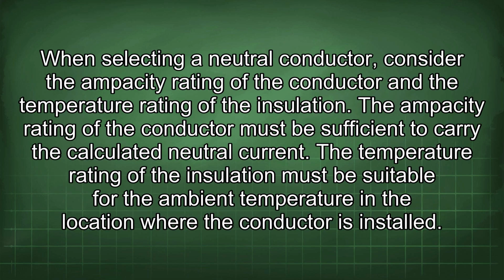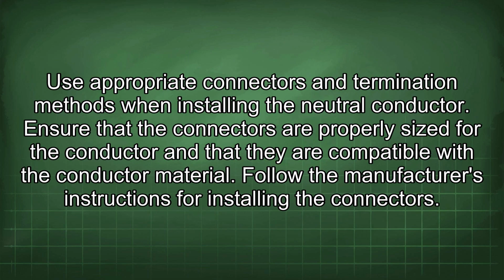When selecting a neutral conductor, consider the ampacity rating of the conductor and the temperature rating of the insulation. The ampacity rating of the conductor must be sufficient to carry the calculated neutral current. The temperature rating of the insulation must be suitable for the ambient temperature in the location where the conductor is installed. Use appropriate connectors and termination methods when installing the neutral conductor. Ensure that the connectors are properly sized for the conductor and that they are compatible with the conductor material. Follow the manufacturer's instructions for installing the connectors.